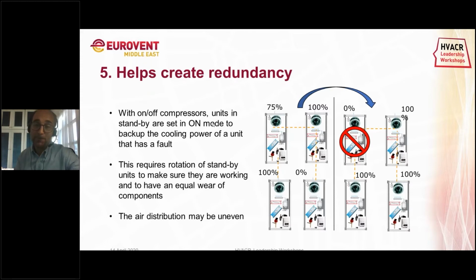Normally, see, this is a very typical layout of a data center. In this example, we have 3 units running and 1 in standby. To have 300%, this normally might result in an uneven air distribution, and then you need to create complicated logics to rotate these units, so that when one unit fails due to any kind of issue, in this example we have an N+1 configuration, the standby unit turns on.